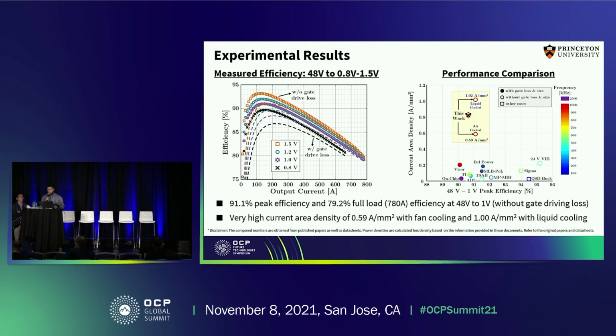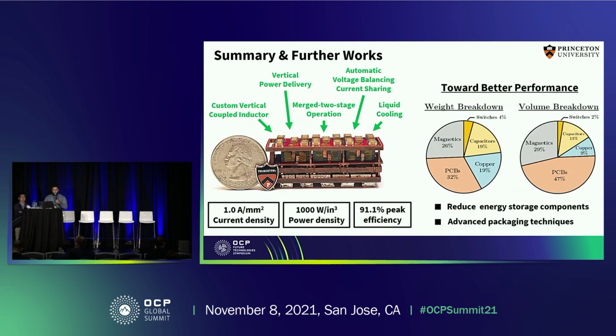To our knowledge, this is actually the highest power density that's been reported for these 48 volt to 1 volt converters. To wrap everything up, we leverage the merged two-stage architecture that JL explained. We use vertical power delivery and a customized vertical coupled inductor, as well as liquid cooling, to achieve 1 amp per millimeter squared current density, 1000 watt per cubic inch power density, and 91.1% peak efficiency.